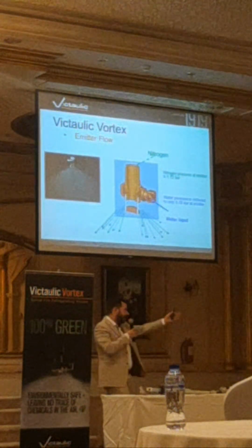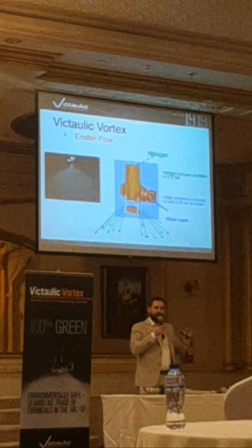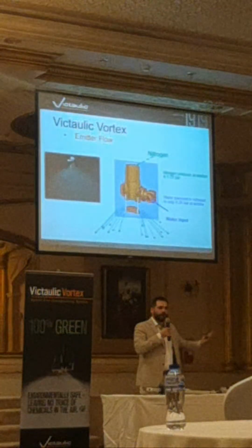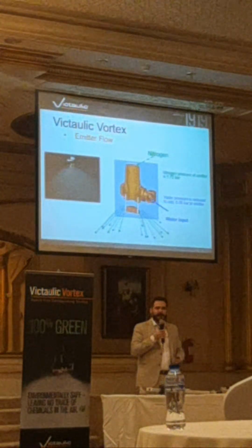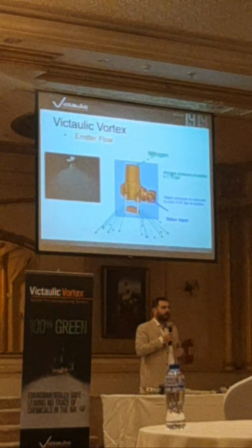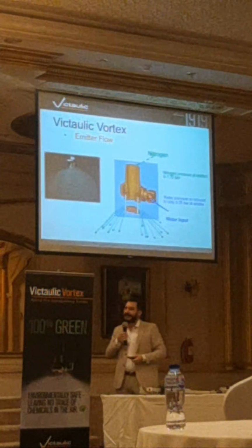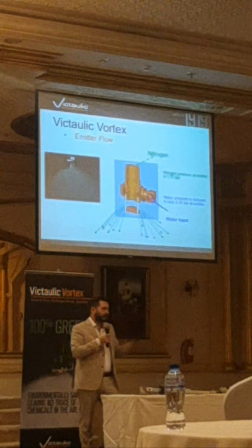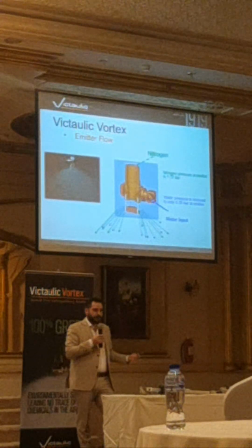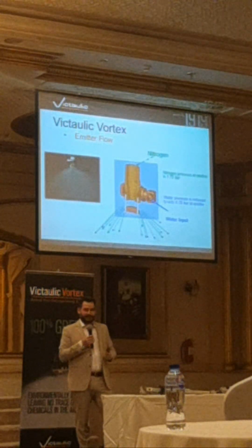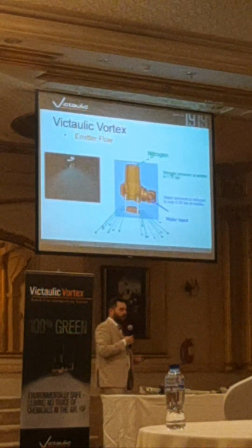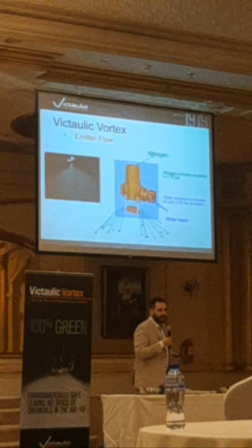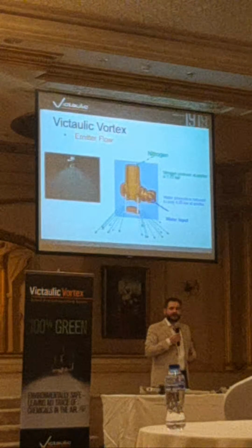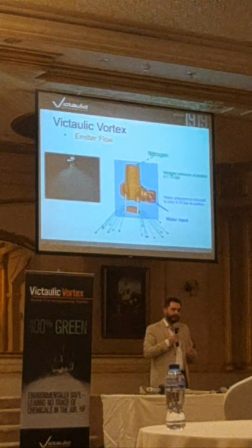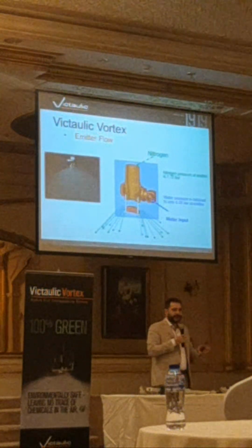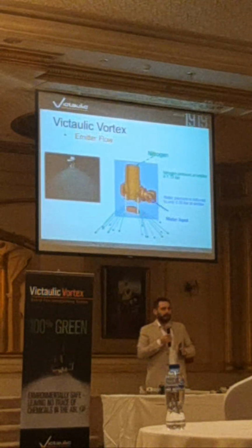That is why an open door can be ignored. Now, to be honest, we're not saying please open all doors and windows because there's a fire going on and it's a vortex. No, we're talking more about permanent openings like cable ducts and electrical work. If you drill a hole through a wall, then you have a permanent opening. There are a lot of gas systems being installed today that are not really maintained properly. Normally, according to the standards, you would need to do a door fan test on a yearly basis to check: am I still in range? Is my system still going to work?